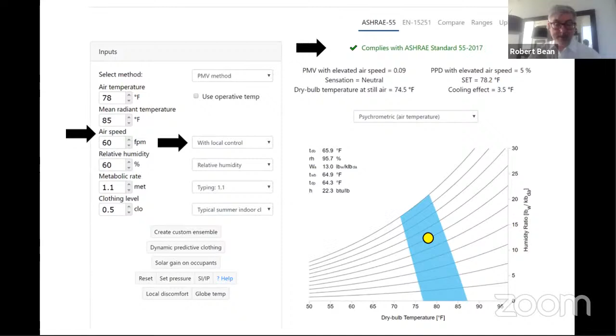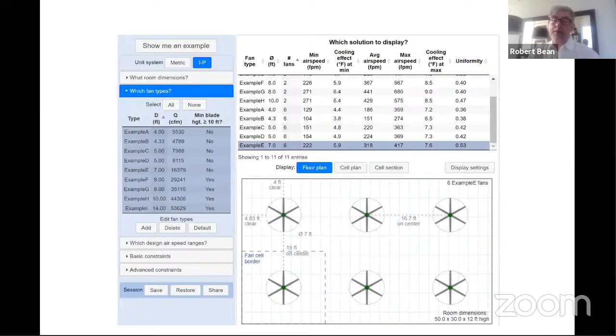And we could do an assessment of that using another tool that's available through the Center for the Built Environment, which is a new tool in the last couple of years, which allows us as application engineers to take a space and break it up into areas, and we can locate ceiling fans. Either we can condition the area with one large ceiling fan or multiple ceiling fans, and we can see the consequences of that. And so we can look at what happens to the air velocity directly below the ceiling fan itself, or as we move further and further away from the fan, what are the consequences?